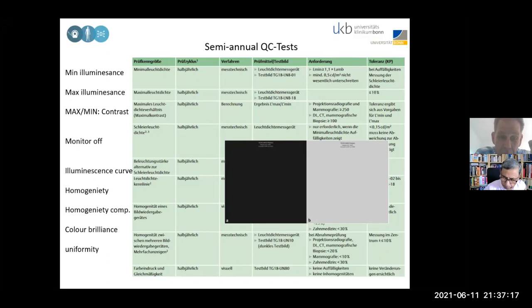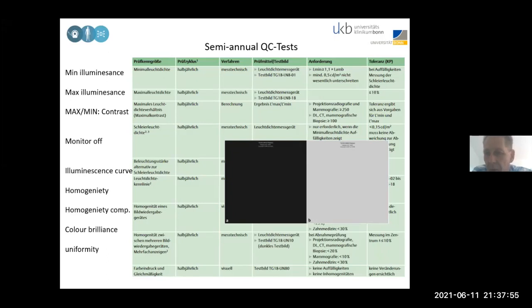Then you check the homogeneity, and you should check the homogeneity of all your monitors among the monitors. We usually have more than one site where you look at your images, and you check that if you are sitting in one room and then in the other room, you see the same or something comparable. Then you have to look at the color brilliance or the grayscale brilliance. You have to check that, and the uniformity of the images. For the uniformity, you see those test images, the black one and the white one, and you have to see whether on your screen this is a homogeneous image or not. Homogeneous means your luminescence should not vary more than 10%.